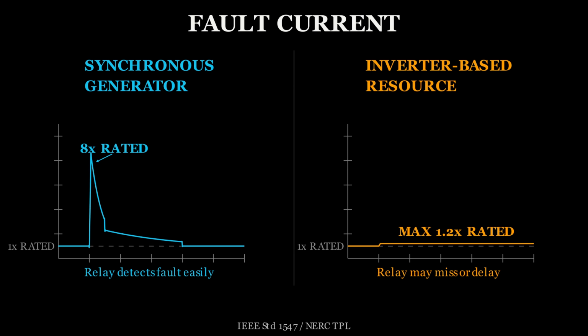Solar inverters and wind converters are different. They're built with power electronics that protect themselves by limiting fault current, typically to 1.0 to 1.2 times their rated output. The protective relay sees a much smaller signal. Detection is harder. In some configurations, the relay may not detect the fault reliably at all.